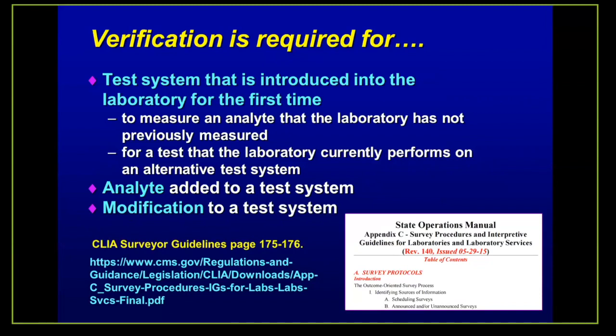Verification is also required for an analyte that's added to a test system, or if we do some type of modification to a test system. And this information is found in the CLIA Surveyor Guidelines, pages 175 to 176. We have a link there at the bottom of the slide. Anyone who has an interest in the quality practices for their laboratory, this is a good section of this document to take a look at, to refresh yourself with.